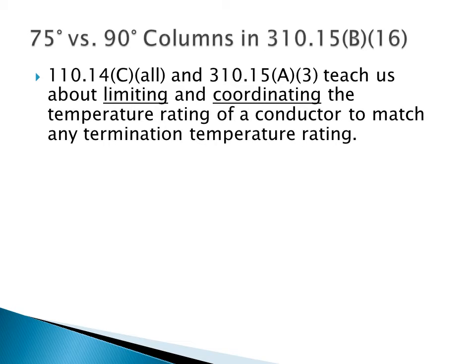These are a couple of codes that I would encourage you strongly to highlight. 110.14(C), all of it, including its subsections, and 310.15(A)(3) teach us about how the temperature rating of a conductor has to be limited and coordinated to match the temperature rating of any termination.